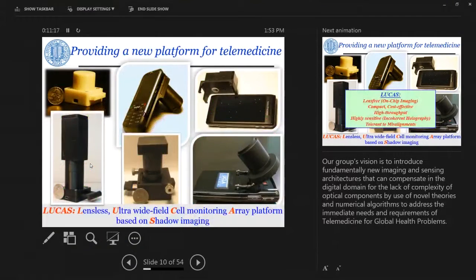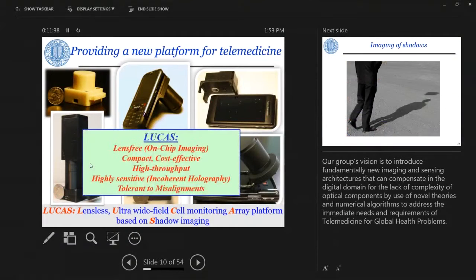Now I'd like to spend a few minutes talking about some of these devices — they're not just miniaturized, they have unique physics and engineering behind them. I'll start with microscopy. Some of these devices convert the phone into a microscope, or are standalone portable devices using the CMOS imager. They work based on unique physics: they don't use any lenses. Between the sample and the sensor there's no optics — it's optics-free — and everything is complemented by computation, which is why they're very compact.